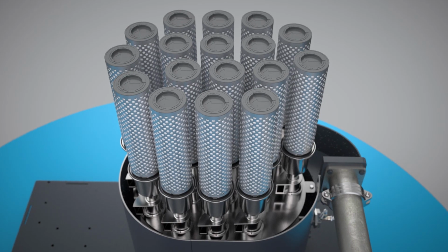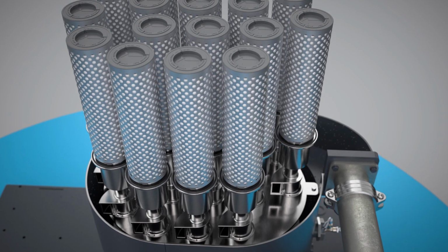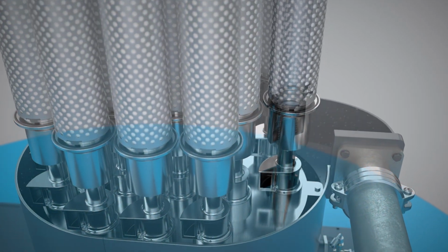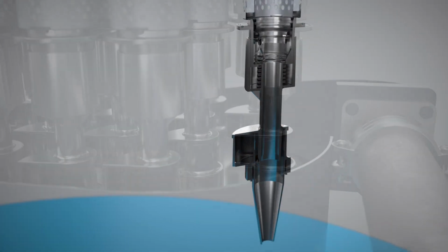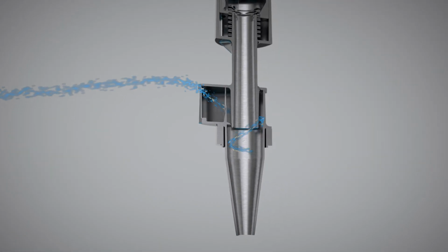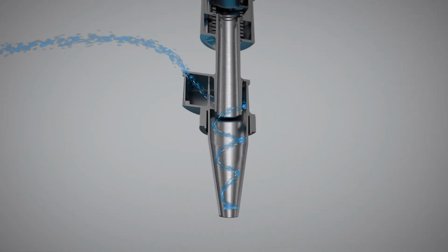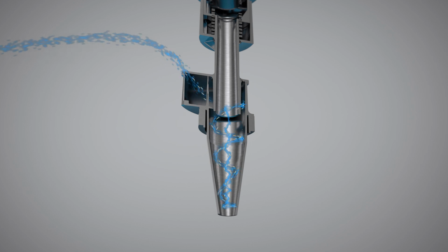The same basic principle is used for the second stage. The flow of oil and air is split into a number of different cyclones. The partially cleaned air and oil mixture enters a cyclone and is whirled around. The smaller dimensions produce even higher centrifugal forces. Again, the collected oil drips down in a separate reservoir. The cleaned air is discharged from the top of the cyclone.